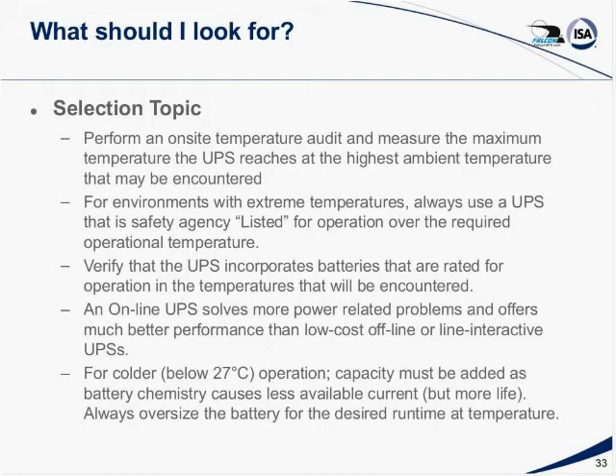Okay, Larry, before we go forward, a question that came in is: explain to us why the battery and the UPS both have to be rated for the temperatures you're talking about. Okay, first of all, when a safety agency evaluates the UPS, it's evaluated with the battery. In the case of a standard VRLA battery or the new technology, the plastics used in the battery are only rated up to 55C, whereas the metal case batteries are rated up to 65C. That's one issue.